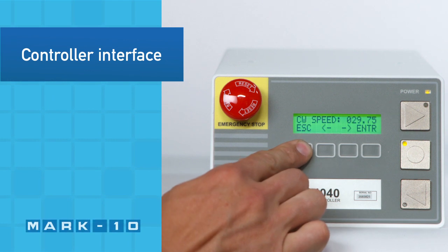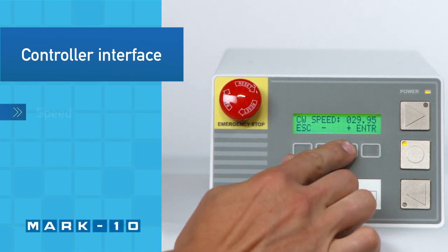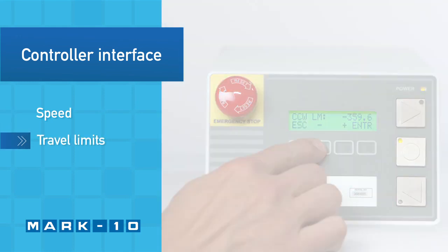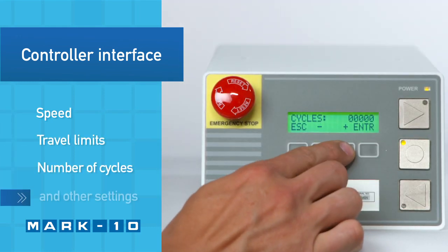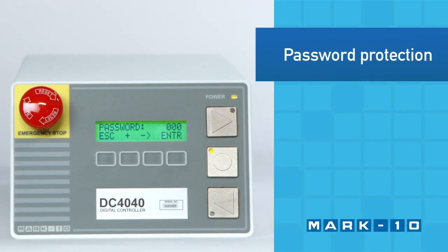Utilizing the simple controller interface, set up test parameters such as speed, angular travel limits, number of cycles and other settings. Password protect the menu to prevent unauthorized changes.